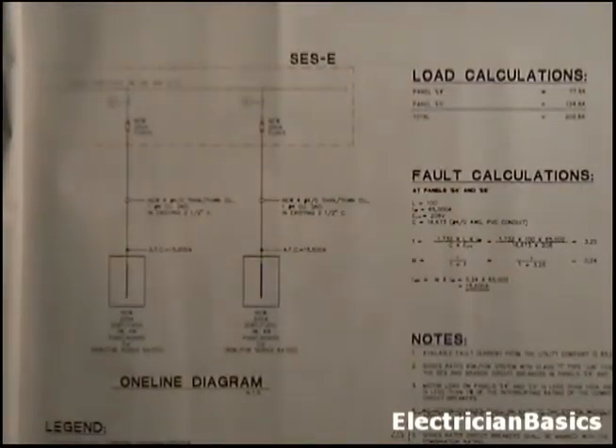The one-line diagrams aren't concerned whether or not it's overhead or underground or whatever. They just want to show the path, and they always show it in a straight line. They don't care if the conduit has to have turns in it. They're just showing a straight line connection. This is something to point out. The conduit was underground most of the way, but you have to pull the wire. It tells you the size of the wire to pull into each of these panels. And these panels, of course, were side by side, and we saw that on our power plan as well. That was, I believe, sheet E4.1. You can look at that in the storage room.